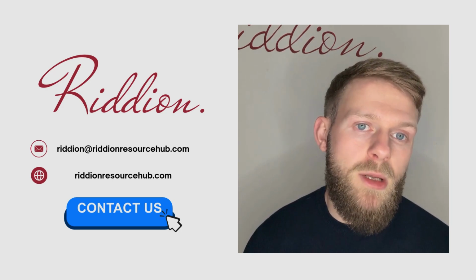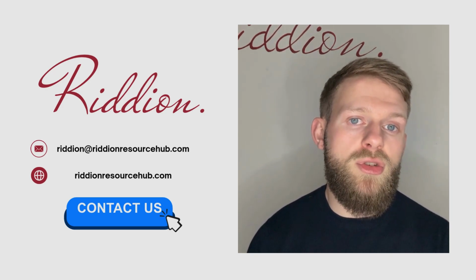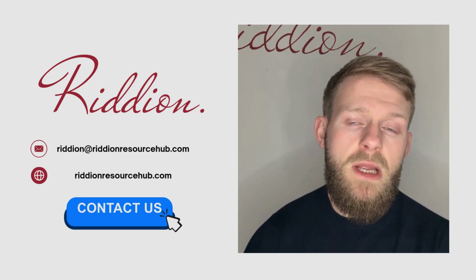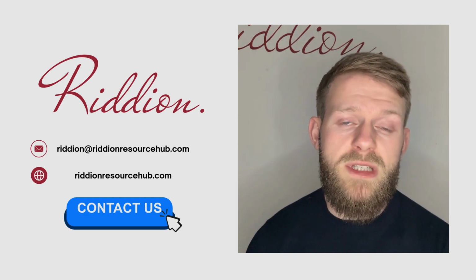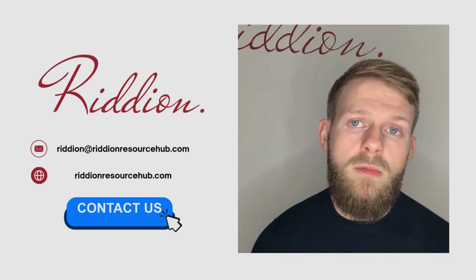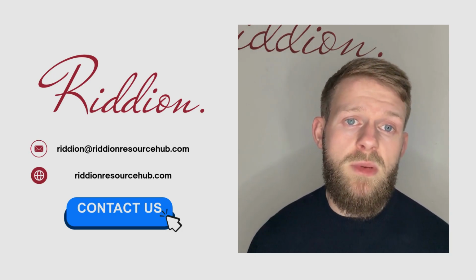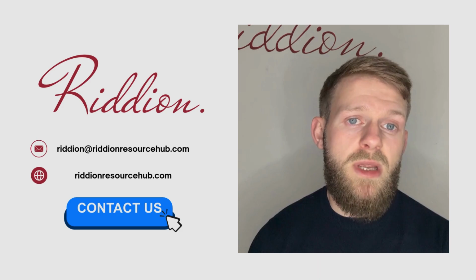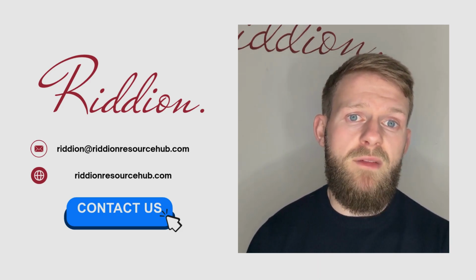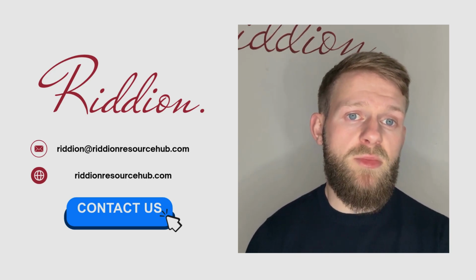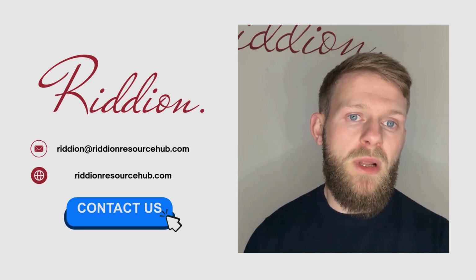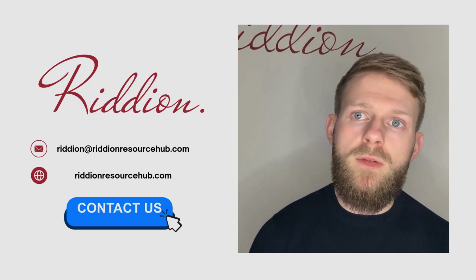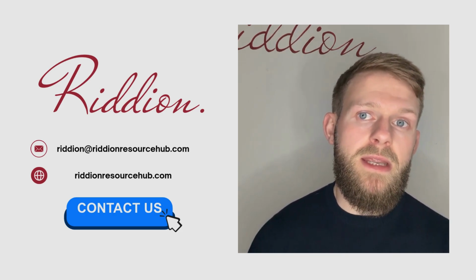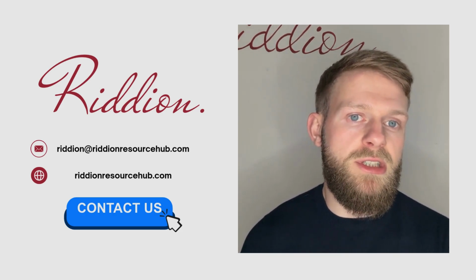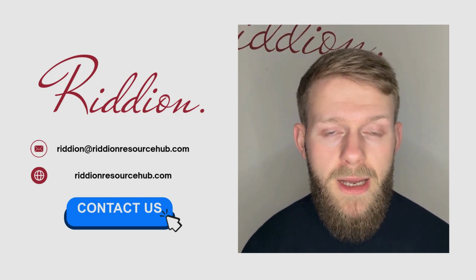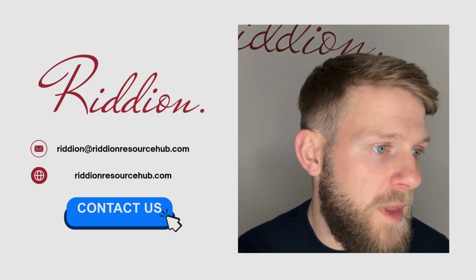Two would be incomplete technical documentation. So if your clinical evidence or risk assessment reports don't meet MDR standards, you'll be sent back for revisions, which again can add months to your timeline. Three would be lack of post-market surveillance planning. Notified bodies are now scrutinising PMS plans more than ever. So if you don't have a robust system for monitoring your device's performance after approval, your application may be put on hold. So if you want to avoid these delays, the key is essentially meticulous preparation and early engagement with the notified body again. Can't advocate that enough. Next question.